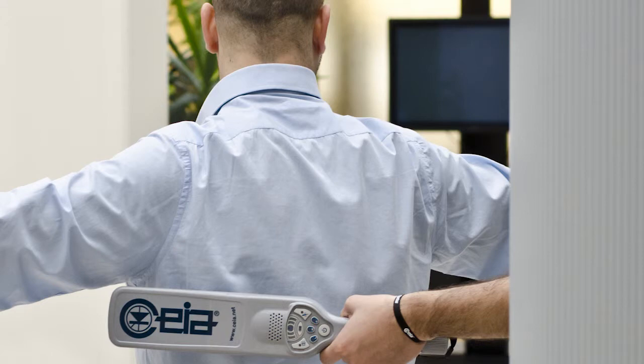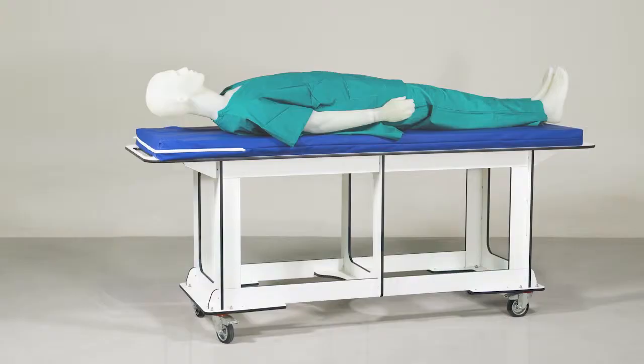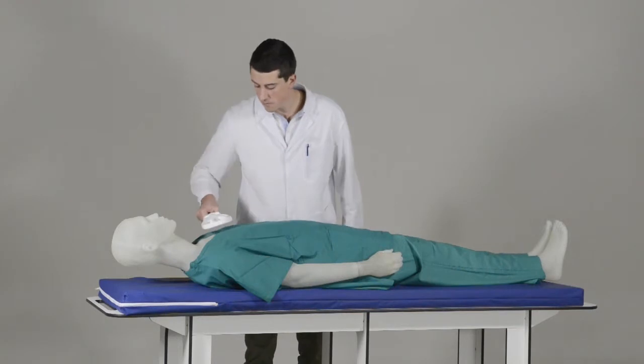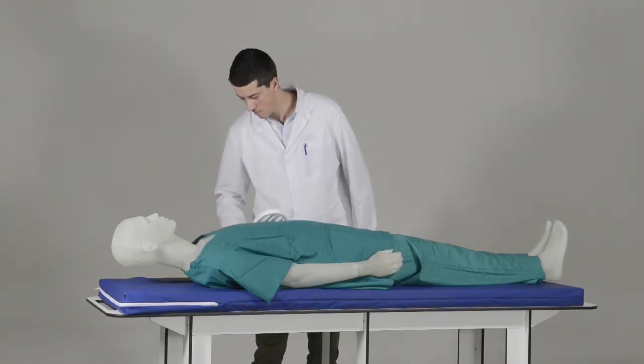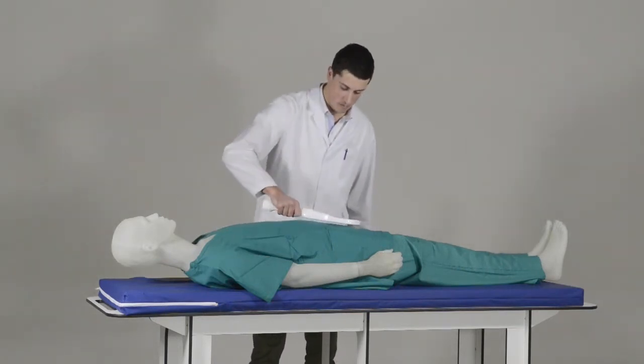Before starting the screening process, it's important to understand that while the PD240CH looks similar to traditional handheld metal detectors used for security screening at airports or public venues, it's operating at a much higher sensitivity and should not be used in a way as observed for those types of applications. In order to use the device to its full potential, the patient should be lying on a metal-free structure or in a standing position. Since the device is being used to detect very small magnetic metal masses, it is extremely reactive to large magnetic metal masses.